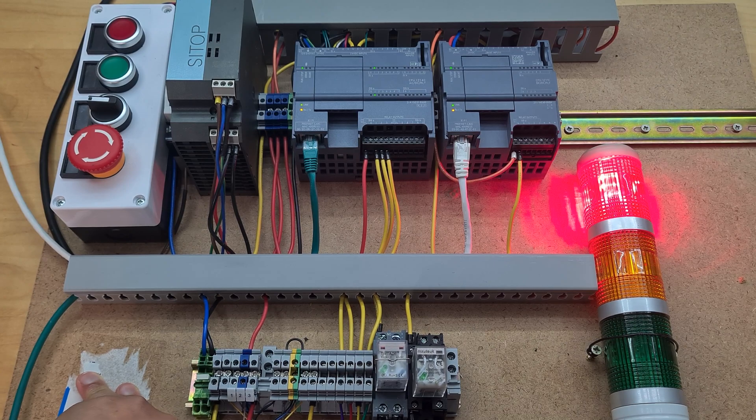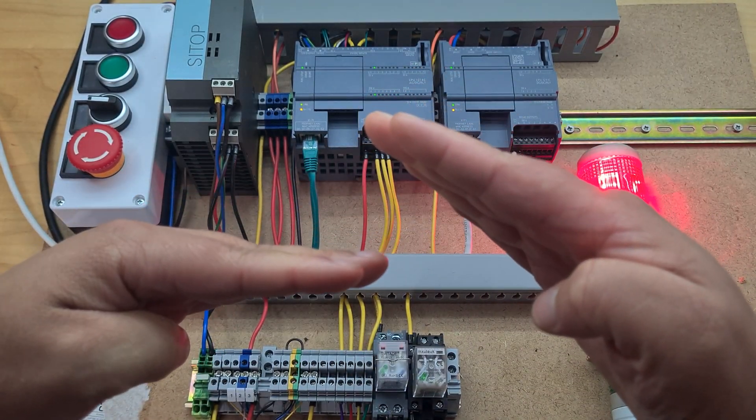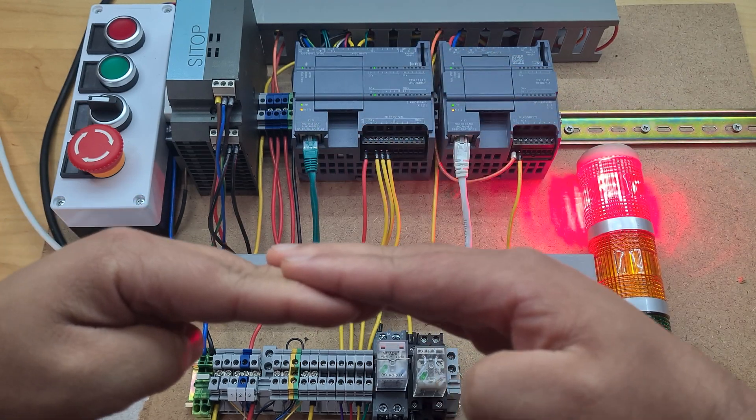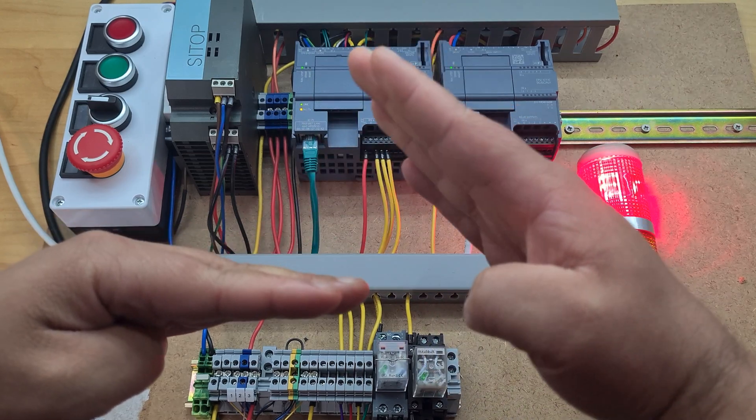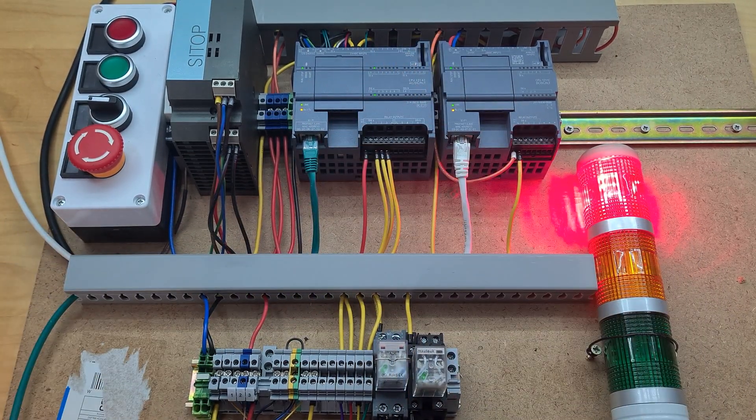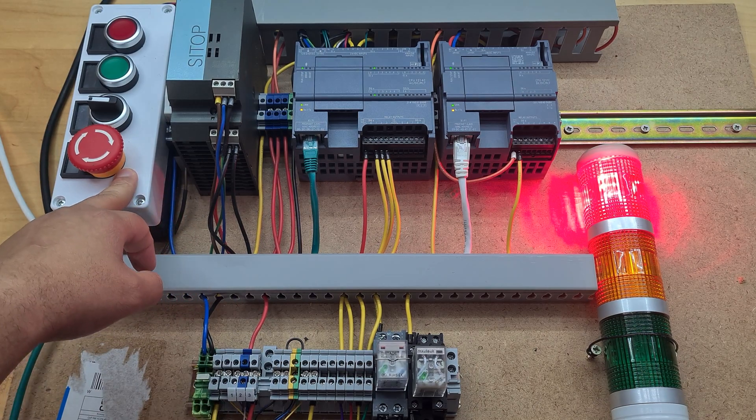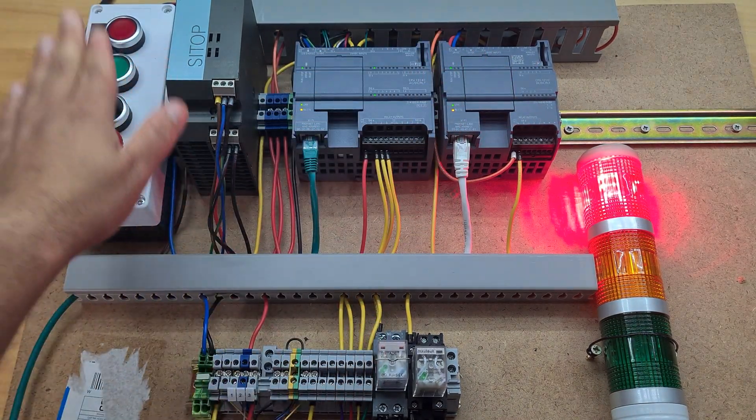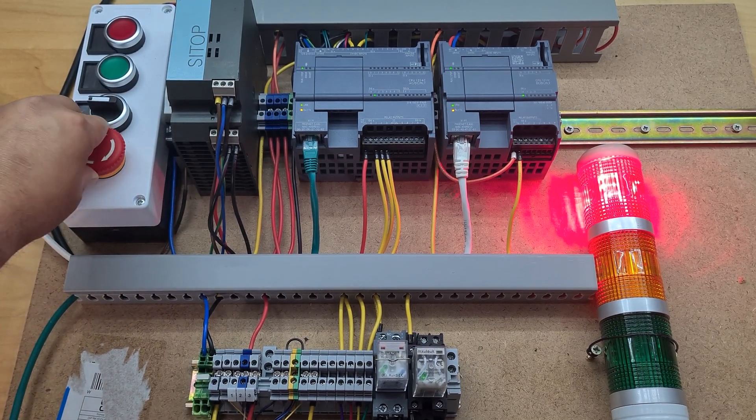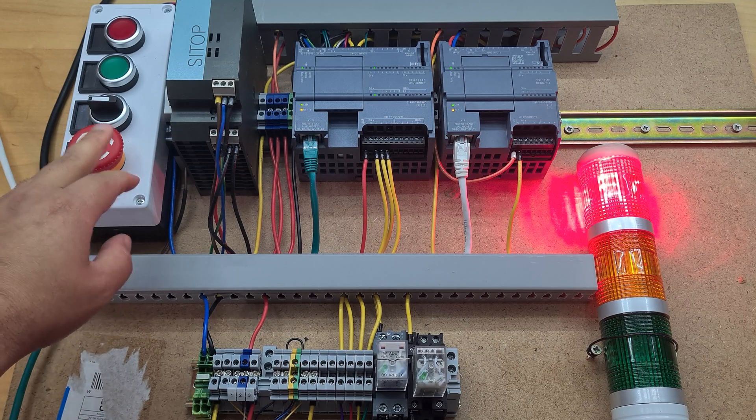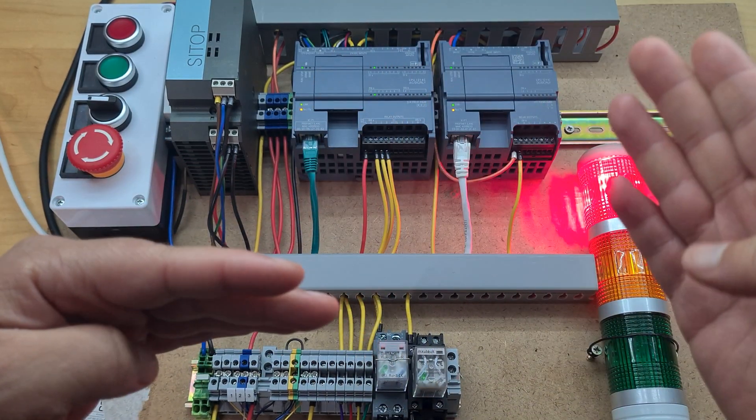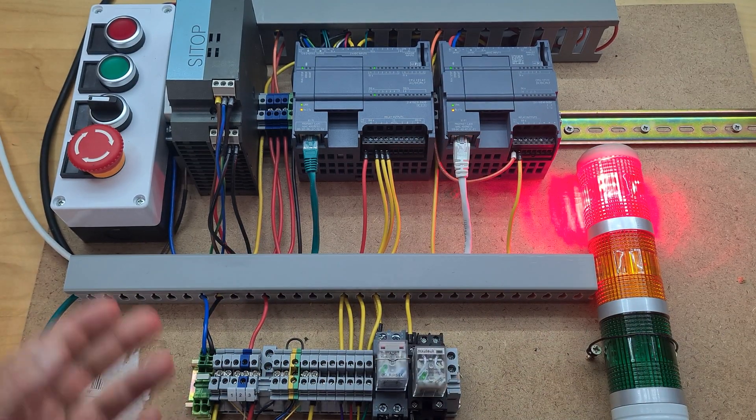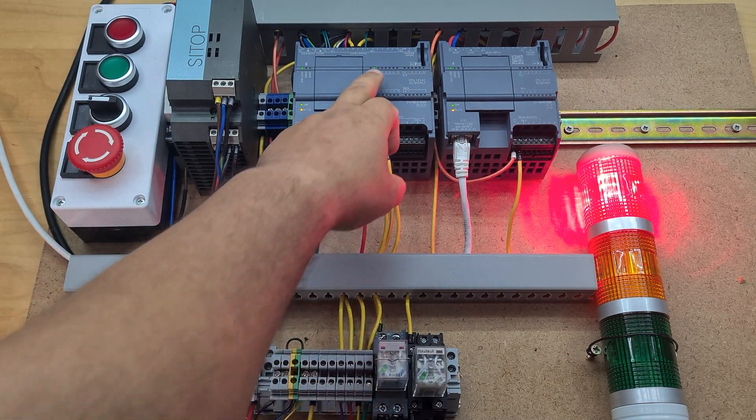Someone in the comments, thank you very much for this, told me that obviously E-stop should be wired normally closed. That is to say that you've got a switch for the button - instead of having it that when you press the button it closes, you want it so that the button is closed and then when you press it, it opens. That way if the wire drops off you know about it. You don't want the wire to be broken and then someone goes to hit the E-stop and it's not working because the wire has been broken for a year and no one's noticed. At least with it being normally closed, when the wire breaks then your E-stop will go off and you'll know you've got an issue.